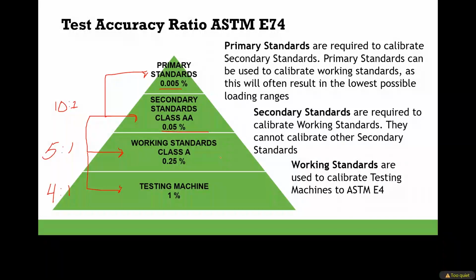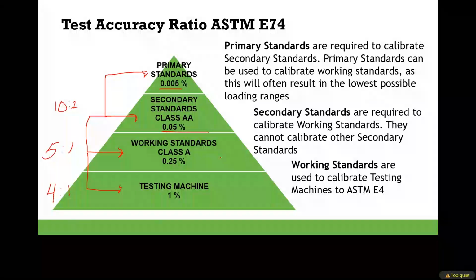your ranges are such that we've inherently built this into the system where I calibrate this load cell following the standard. Hopefully I send it to Morehouse for dead weight or NIST or wherever. I get my cal back, I put it in my machine. I know at least Morehouse gave me they were 10 times better. Then when I do these other cells, I have my class AA, and by the description of the standard, multiplying by 2000 and whatnot, I know that I'm 5 times better than what I'm going to calibrate for another customer when I multiply their results by 400.